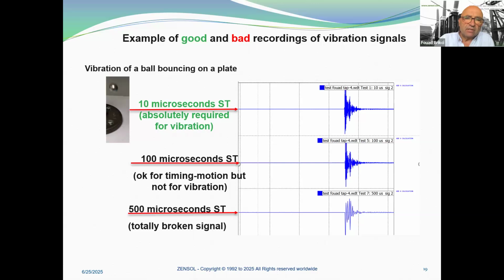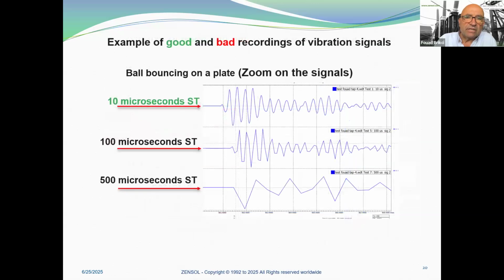And here, just to compare, is a 500 microsecond sampling time, and we got a totally broken signal. In the next slide, you will see the zoom of each part. With 10 microseconds, you can see a smooth signal, absolutely clean. At 100, the signal starts to be broken, and at 500 microseconds it's totally broken. You can understand nothing on this signal. It's just noise.